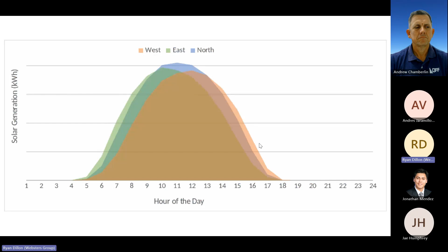Coming back to this case study, we'd had someone with an initial contract signed for 330,000 for a 200 kilowatt system. It was quite staggering what the value proposition in this opportunity was, and what the benefit is of investing in an energy audit. In this scenario, from a financial perspective, it was 330,000 upfront for the solar system at a 200 kilowatt scale, which would save 31,200 in year one based on current Ergon Energy pricing. Over 15 years, that would have a 7% return on investment.